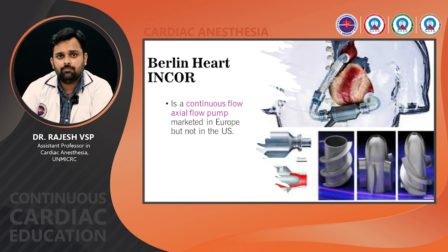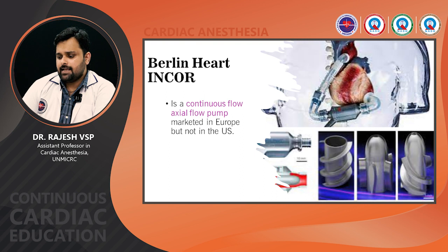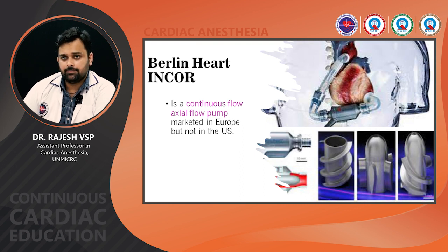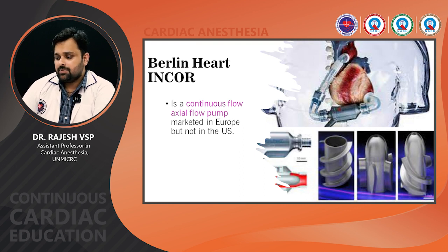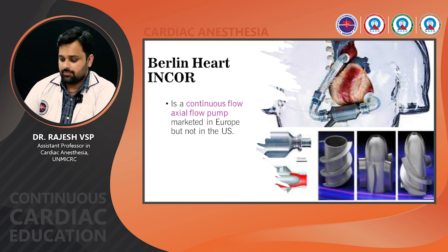The next is Berlin Heart Incor. This is also a continuous flow axial flow pump, and it is marketed only in Europe but not in the US. As the blood passes through the Incor, it first passes an inducer that directs laminar flow onto the impeller, which is suspended by a magnetic bearing and floats free of contact with other parts.